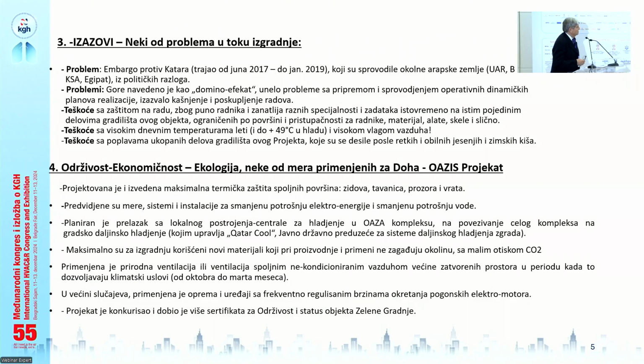Also, a problem was the high temperatures in summer. There are practically two seasons: a hot season from around the beginning of April to the beginning of October, and a cold season. During the hot season, temperatures, despite the design value per Qatar construction specification of plus 47 degrees Celsius in shadow, sometimes reached 49 or even 50 degrees Celsius in shadow, as you'll see in some slides.